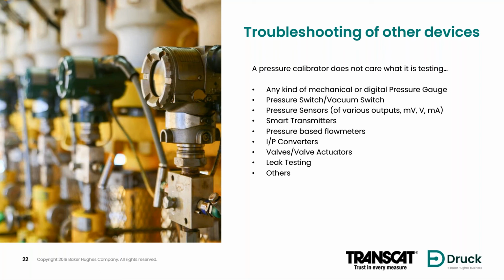We see those in various industries: smart transmitters, pressure-based flow meters, current to pressure converters, valves, valve actuators, leak testing functions. There's oftentimes pressure decay based leak testing functionality or tasks. It's probably as long a list as you can think of for pressure based devices. A portable pressure calibrator can help you in troubleshooting and identifying root cause errors of those.